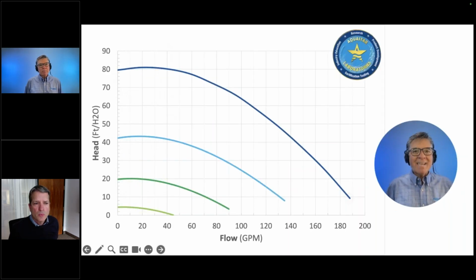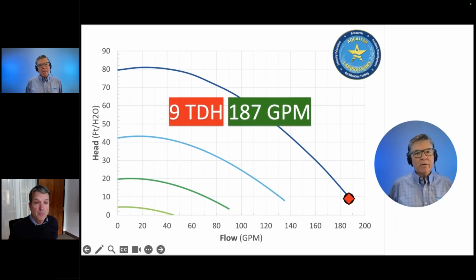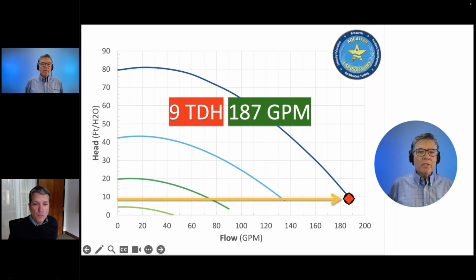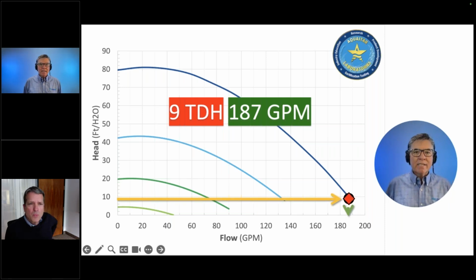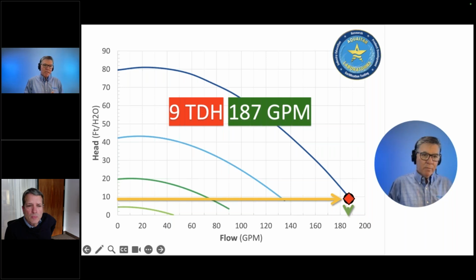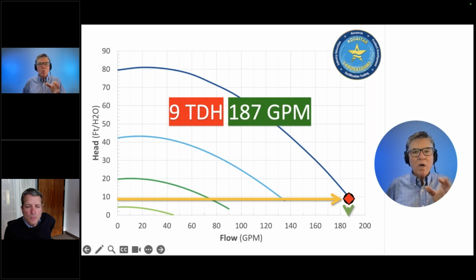Now let's look at this on the pump curve. We go to 9 TDH. It's way out at the limits of this pump, which is why I have the data. You can see it's up here at 187 gallons a minute, same pump. The reason I wanted to show this is if you have AHJs or code officials saying you have to use the max flow of the pump to confirm VGBA compliance, you can't get there. It causes all kinds of problems. That's multiple seminars in and of themselves. But measuring TDH is why I mentioned the health departments. If you actually measure what you have and document that, then they will accept the actual flow rate instead of this theoretical flow rate, especially for drain cover and VGBA compliance.